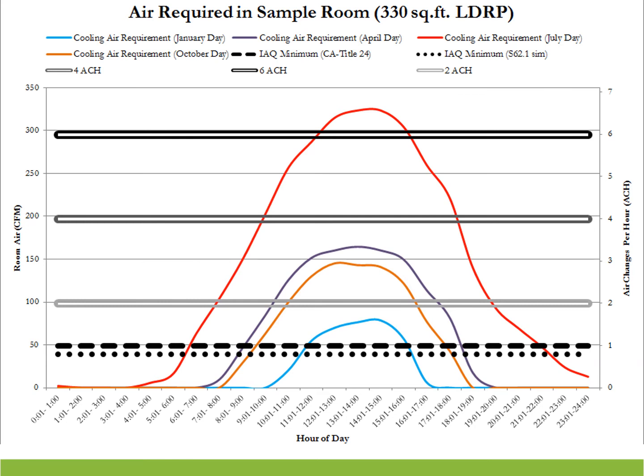But the real kicker is the line up at the top — that's 6 air changes per hour, way up there. That's kind of appropriate for a summer afternoon, but the rest of the year we are over-ventilating that space. Here's the amount of over-ventilation we're doing on a summer day, and here's the amount on a winter day.